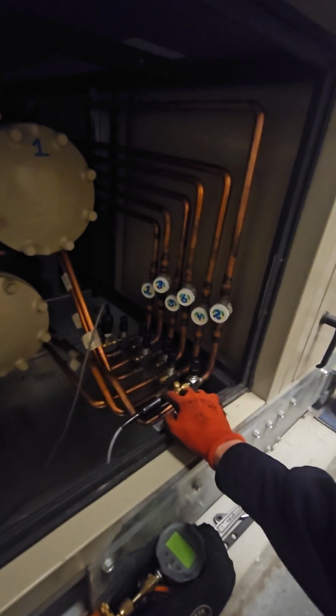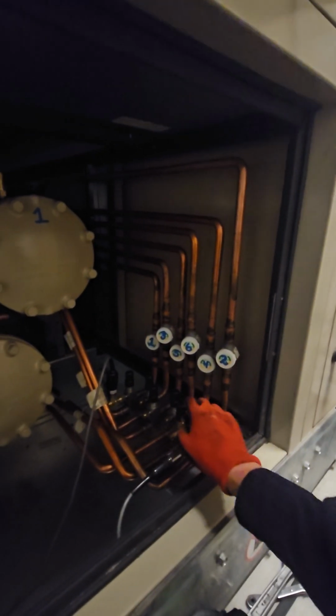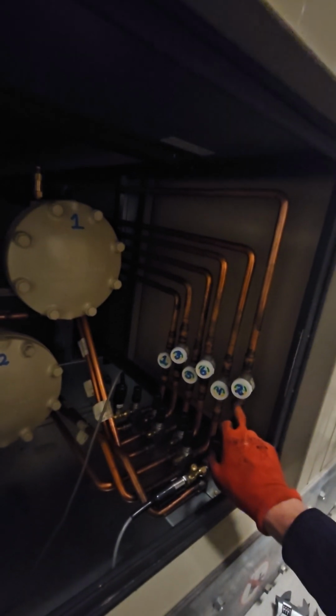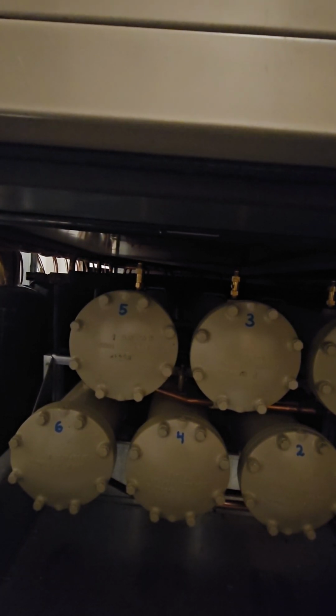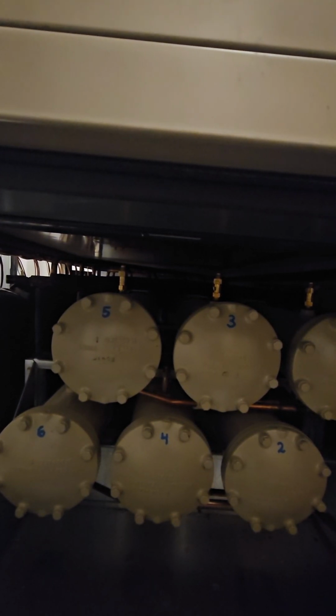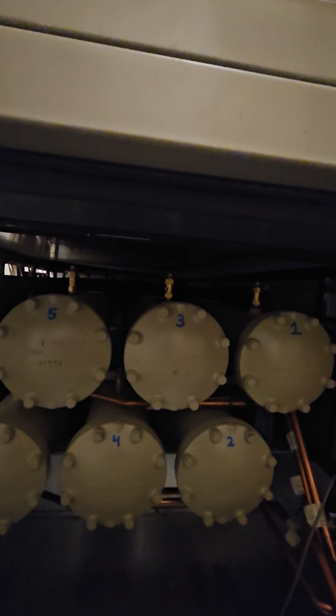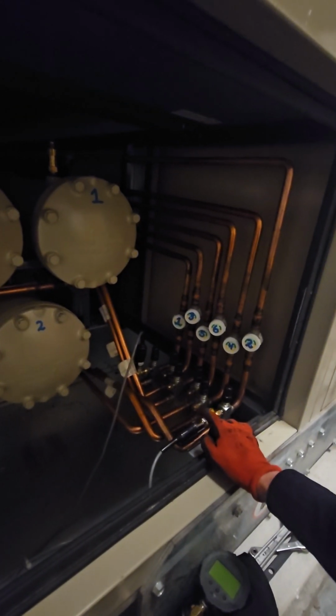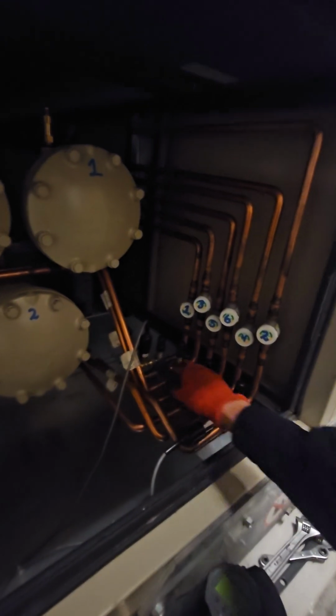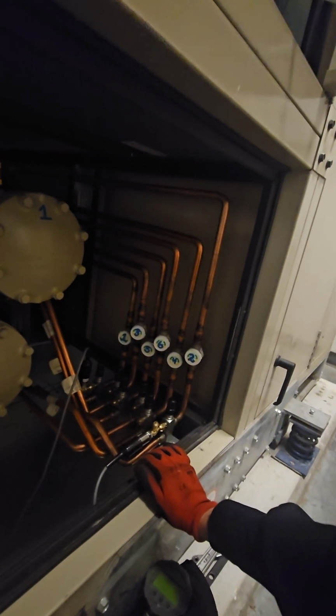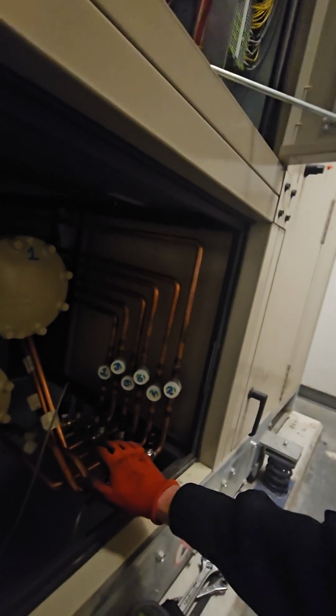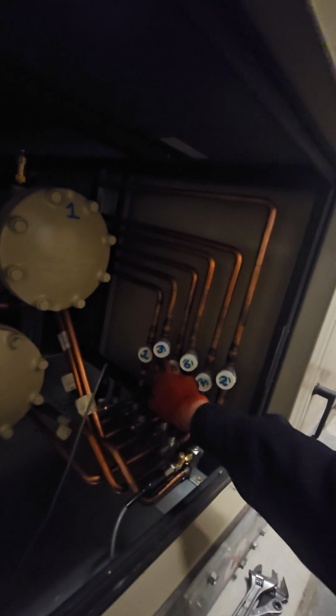These ones also, if you'll notice, you can see the transducer on number 1 and number 2. The reason why we have that is we have a water regulating valve, aka a head pressure control valve, but on the water side. It will modulate to try and maintain head pressure, but it only does it on compressors 1 and 2, which, in essence, is how a lot of these are, like 1, 3, and 5.